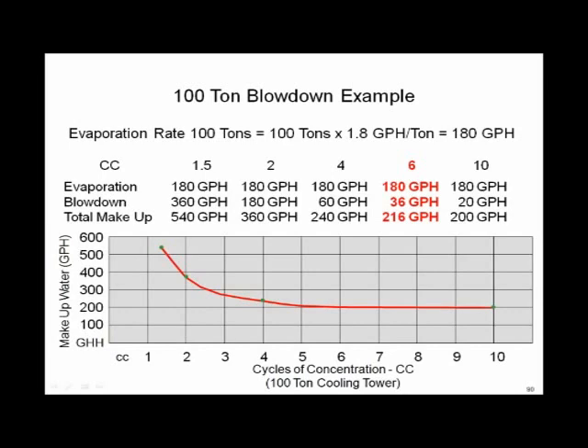Let's just get a quick example of what's going on. But most of the towers I've seen recently, people just had a manual valve blowing them down, with nobody looking at the actual conductivity or the amount of solids in the tower. So here we go. For a 100-ton tower, the evaporation rate required is roughly 15 pounds per ton, for 100 tons. It stays constant. It's 180 gallons per hour across the top, all the way to the 10 cycles on the right.